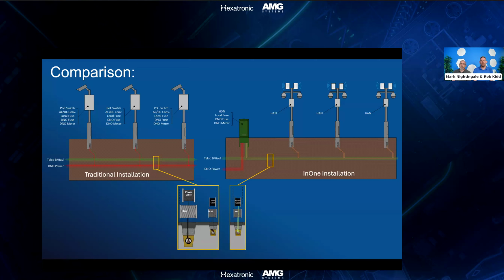If we look at an InOne installation, however, you can see that we can simplify things quite significantly. So a centralized head-end unit where we house our DC conversion, optical connectivity, local fuse, DNO power and meter and all of that, which means that we no longer need to take the DNO power out to each pole within the network.